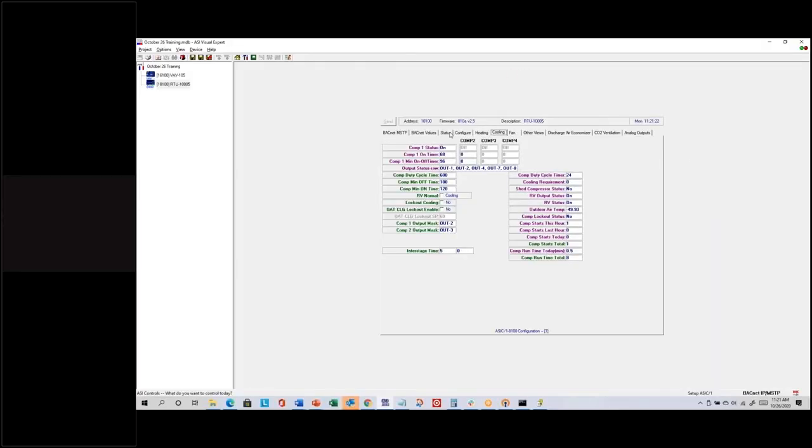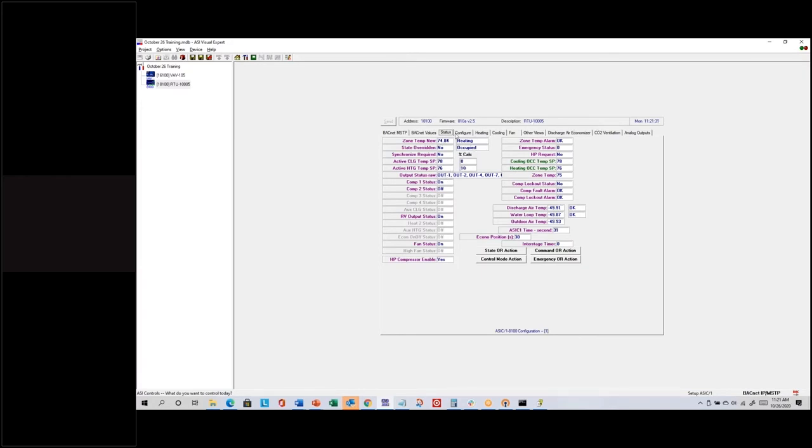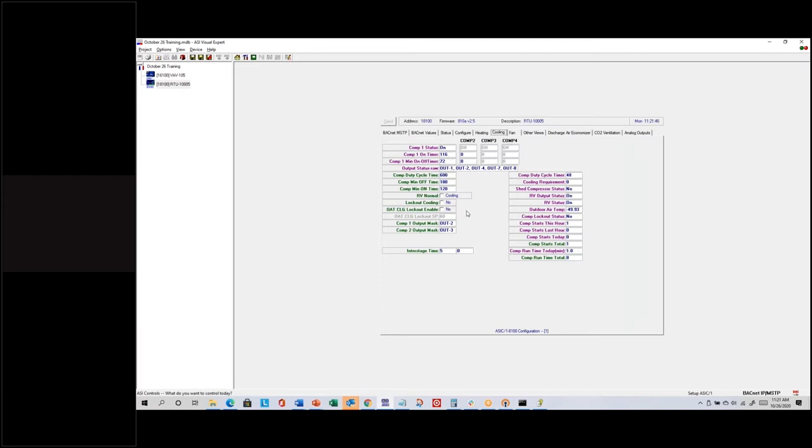We are in the heating case because our temperature is lower than the heating set point, so the economizer settings don't matter anyway. I still see the calculations in the cooling tab. With two compressors, the first stage only cares about the first 50 percent. At a 10 percent heating calculation, the compressor on-time is 16 percent. Once the heating or cooling requirement gets to 50 percent, stage one will be on indefinitely at the full 600 seconds.